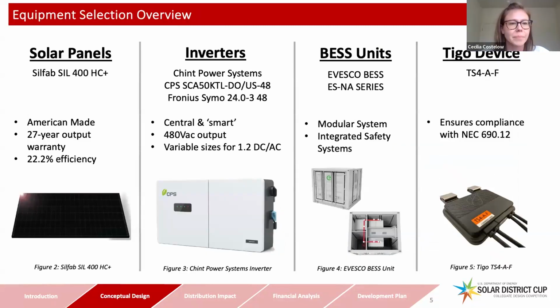Getting into our equipment selection: for our solar panel, we chose the Silfab SIL 400 HC+, mostly because it's American made, allowing us to take advantage of the domestic content bonus. For inverters, we went with 2 manufacturers, Chint Power Systems and Fronius. We were looking for large central inverters with an output voltage of 480 volts, so we could connect directly to the building's distribution panels.